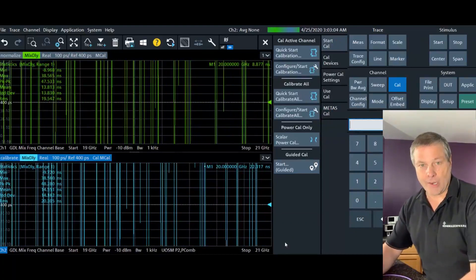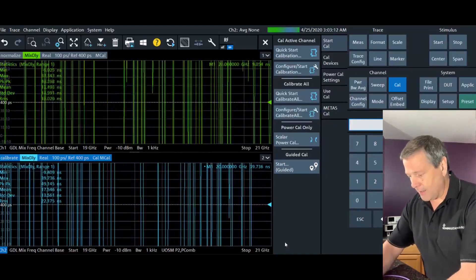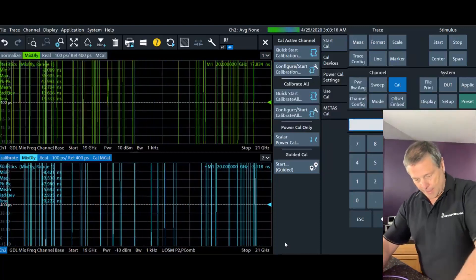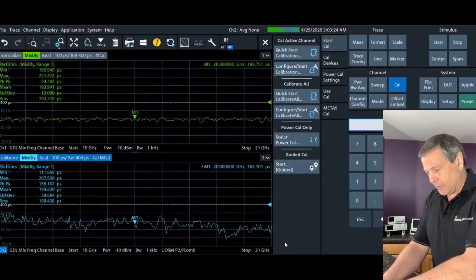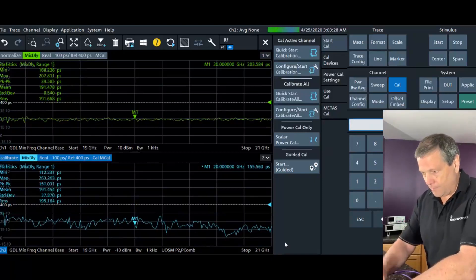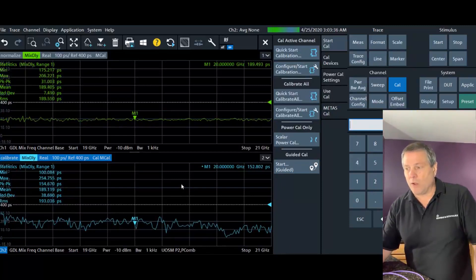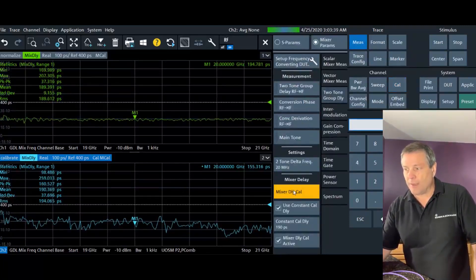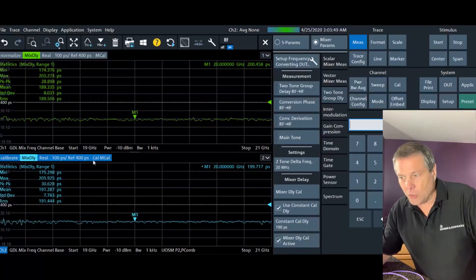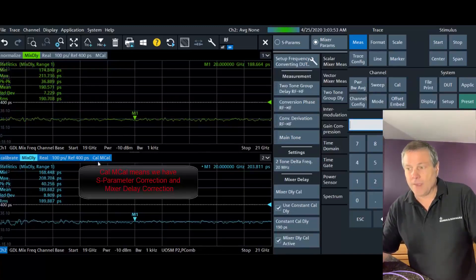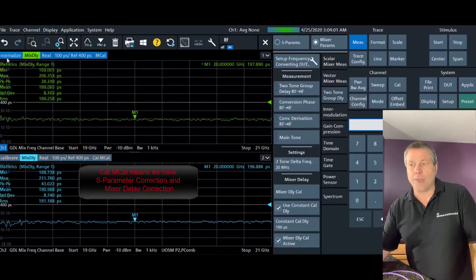Now that I have an error model on the channel, it's going to change my mixer delay calibration. That will always be step two when creating a calibrated group delay channel. I'm now connecting the calibration mixer to the VNA and waiting for the traces to settle. Then I'll recalibrate channel 2 to take advantage of the latest error model. To do the delay calibration, go to the channel, select Measure, Two-Tone Group Delay, and then Mixer Delay Cal. After doing that, channel 2 becomes a nice flat trace — just like channel 1 — but channel 2 now has both a CAL (S-parameter correction) and an MCAL (group delay correction). Channel 1 only has the MCAL, which is essentially the normalization.